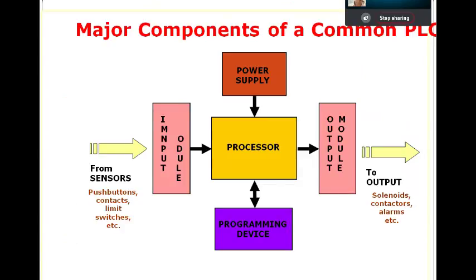If the processor only knows digital, communicating analog to it would be a problem. So the input module converts the analog signal from the field to digital, and sends the digital form to the processor. In the output module, there is again a digital-to-analog conversion, because final control elements operate on analog values like 0–10 volt or 4–20 mA.